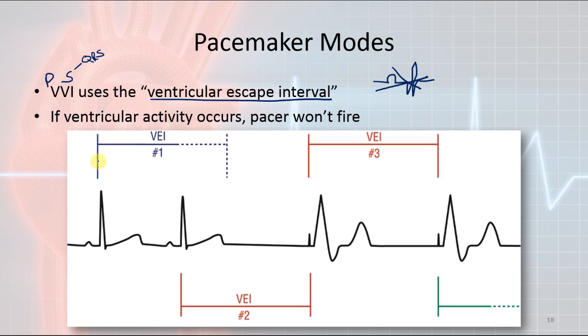So once again, like the atrial escape interval, it will sense whenever there is a QRS complex, and it will start the millisecond timer. If another QRS complex occurs, it will stop the timer and reset it. Now, here's your millisecond timer, and what happened to your timer? It expired. So what did the pacemaker do? It senses the QRS, the ventricular escape interval expired, so it paced the ventricle, giving you a pacer spike and a huge, wide, bizarre-looking QRS. What happened right here? The ventricular escape interval timer expired again, caused a pacer spike, and caused a big, wide QRS complex.